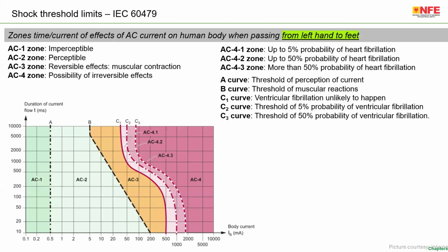Now first is to talk about the threshold limits of the current through the body. I'm sure all of you are aware, and in all our seminars Mr. Krish used to explain the current and time threshold limits in detail to the participants. What is this 30 milliampere? In case of 30 milliampere, what is the duration? 300 milliampere, or 5 times IΔn, 150 milliampere, what is the limit? All these are very well discussed. But please note this zone, the time and current effect of AC current on the human body when passing from left hand to feet. This current of 30 milliampere, which we conveniently say for an RCD of low voltage, is applicable. This current limit is based on the current flowing from the left hand to feet.